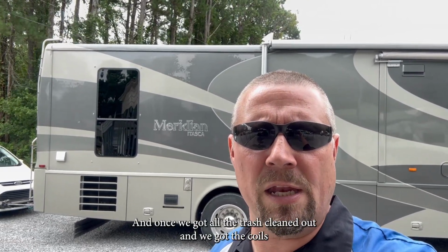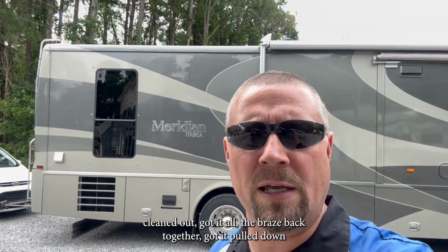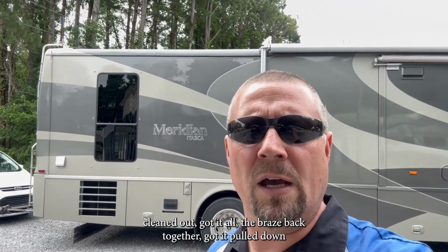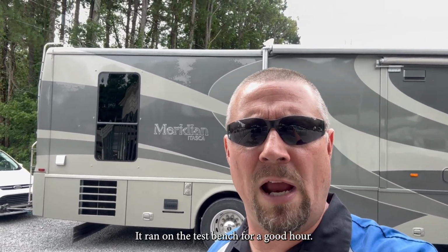Alright, so you can see Mr. Lewis has got this one all finished up. Now, you saw what we were doing on this 6537 yesterday. Obviously had trash in the system, and once we got all the trash cleaned out and got the coils cleaned out, got it all brazed back together, got it pulled down below 500 on the gauge, so it vacuumed down real good. Feel like we got all the trash out of it. Lewis got it all back in, and it ran on the test bench for a good hour. He had 21 degrees differential on this one running in the coach this morning. So another one that's been resolved here at Shelburne RV.